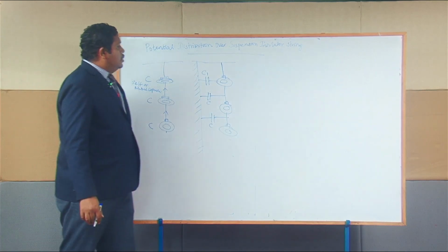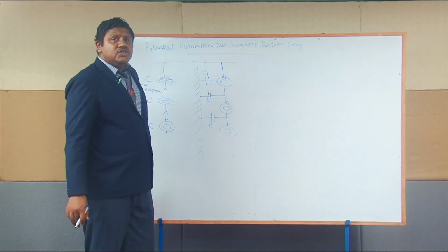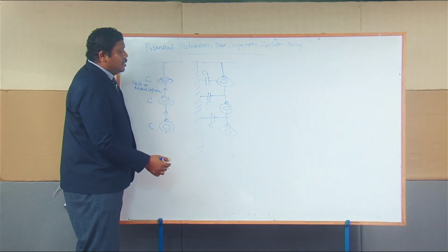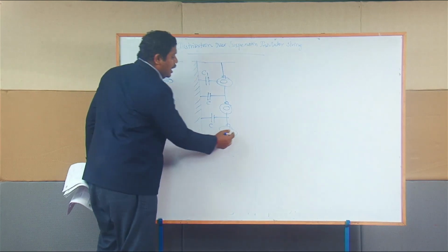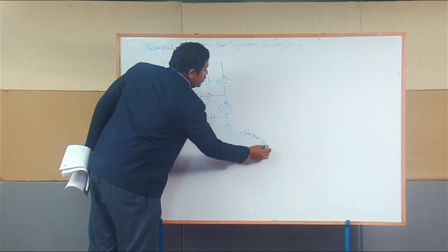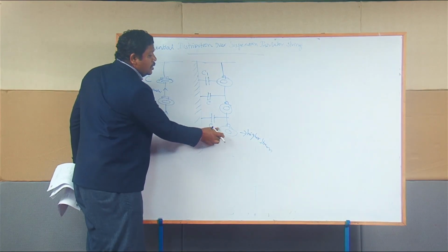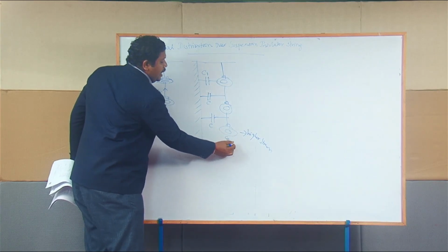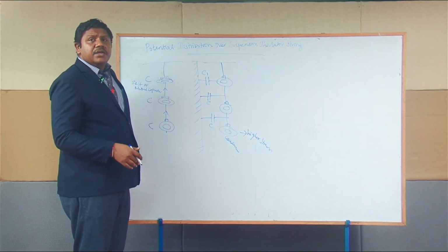Now you are going to see what is meant by string efficiency. While considering the effect of shunt capacitance, the voltage distribution across the string, nearby the conductor, will have higher stress. The porcelain disc which is placed nearer to the conductor will be under high stress, whereas if you go away from the conductor, it gets reduced.